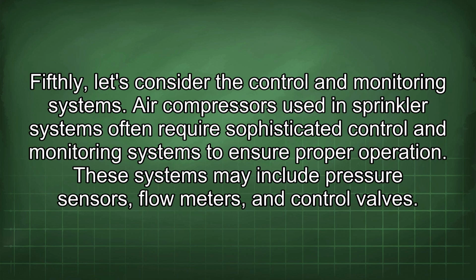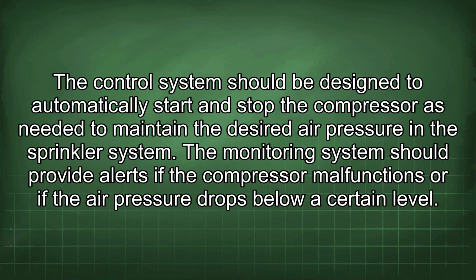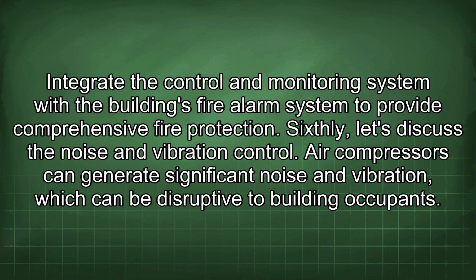Fifthly, let's consider the control and monitoring systems. Air compressors used in sprinkler systems often require sophisticated control and monitoring systems to ensure proper operation. These systems may include pressure sensors, flow meters, and control valves. The control system should be designed to automatically start and stop the compressor as needed to maintain the desired air pressure in the sprinkler system. The monitoring system should provide alerts if the compressor malfunctions or if the air pressure drops below a certain level. Integrate the control and monitoring system with the building's fire alarm system to provide comprehensive fire protection.